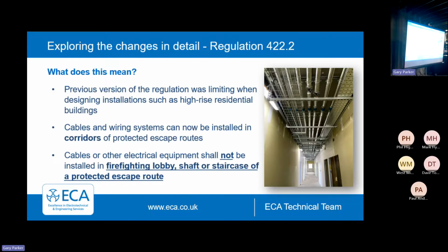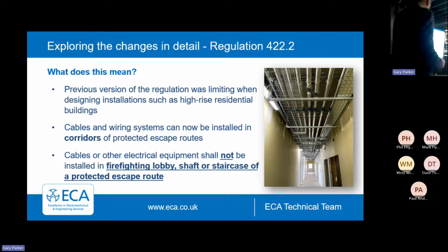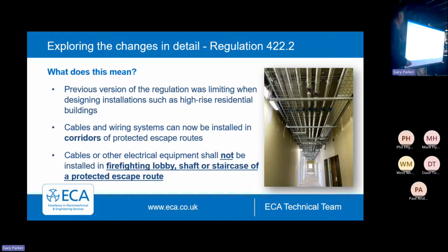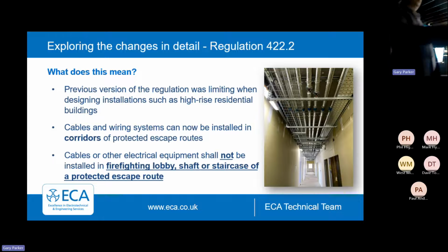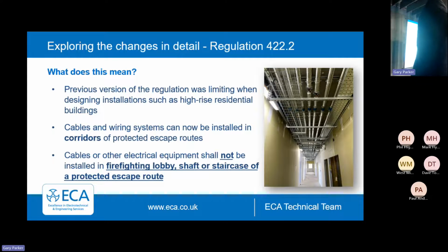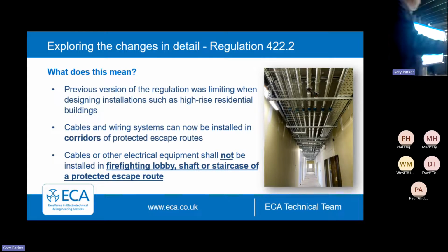The previous version of BS 7671 was always quite limiting, restrictive, and ambiguous. Hopefully it's been clarified that cables and wiring systems can now be installed in corridors of protected escape routes, but cables or other electrical equipment shall not be installed in the firefighting shaft of the protected escape route. So the corridor, fine; the firefighting shaft, the firefighting area, the designated areas - no. Hopefully that adds a little clarity.